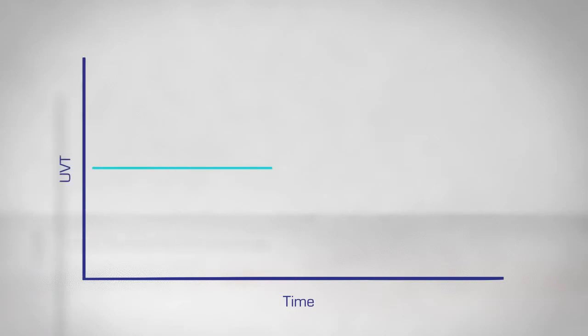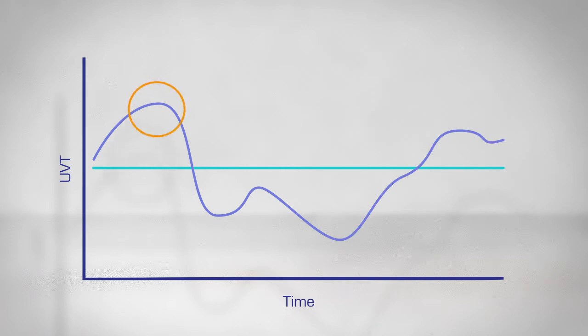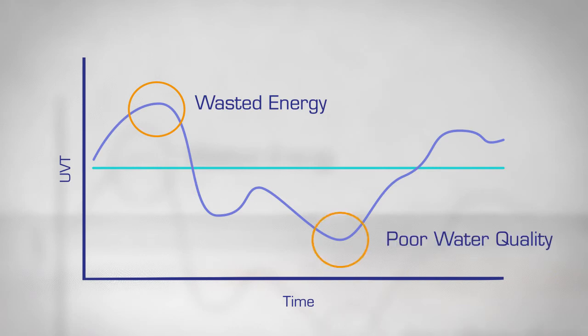Your UV system is designed around the expected UVT of the water, but the actual value fluctuates. If your UVT is higher than expected, you're driving your lamps too hard and wasting energy. If your UVT is lower than expected, treatment may not be effective and your water quality will suffer.